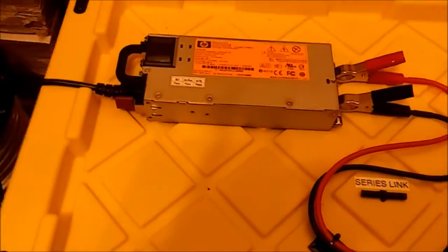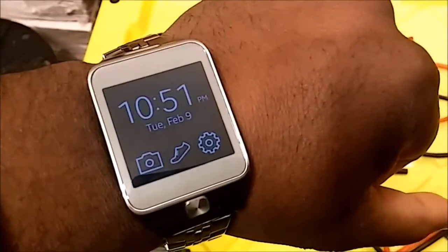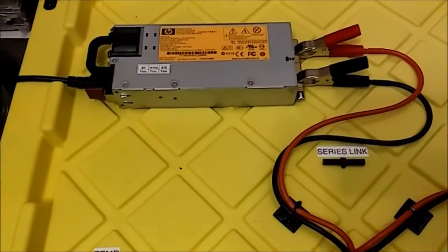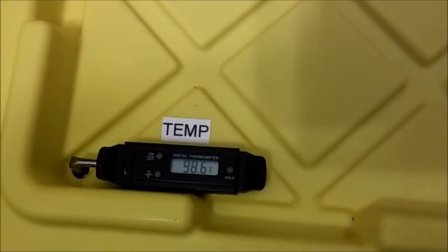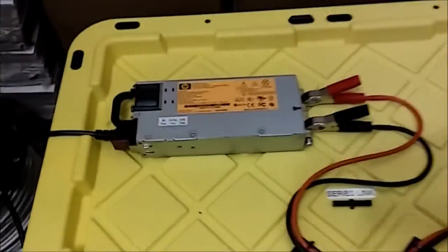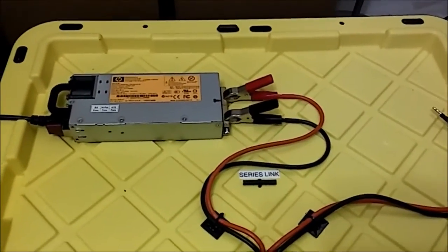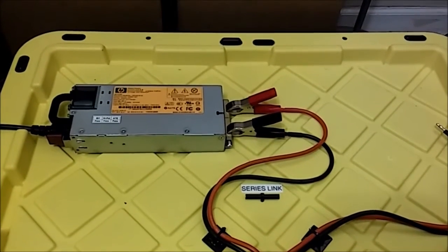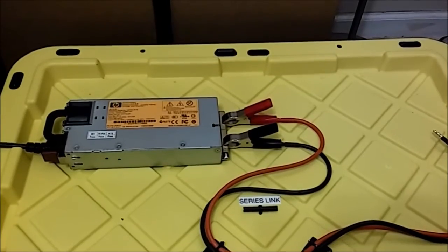Okay, so I'm a little bit over. It is, let's see, 10:51. Power supply is still on my load bank. The temperature rose up to 98.6. So basically, I just demonstrated that the power supply can hold a 45 amp load for two hours.